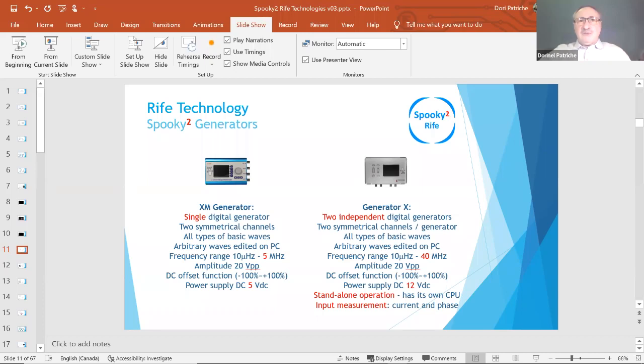You can see the differences between the two generators highlighted in red. The biggest difference is that Generator X has two independent generators in the same box, as well as its own CPU, which allows for standalone operation without a computer. There is also a difference in the maximum output frequency, 5 MHz versus 40 MHz. But there are two things to mention regarding this. First, the XM generator is capable of going up to 25 MHz with software multiplication. Secondly, very few programs use high frequencies, and some accessories like plasma don't work over 3.5 MHz. So, depending on the application, this difference may not be significant.